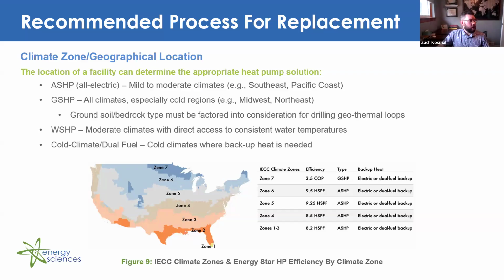So moving on, water source heat pumps. These are typically found in moderate climates with direct access to that consistent water source. And you have dual fuel and cold climate heat pumps, which are typically found in cold climates where backup supplemental heating is needed. So it should be noted that climate zone maps, as shown here in Figure 9, can give you a general idea of how your equipment may operate in your region.